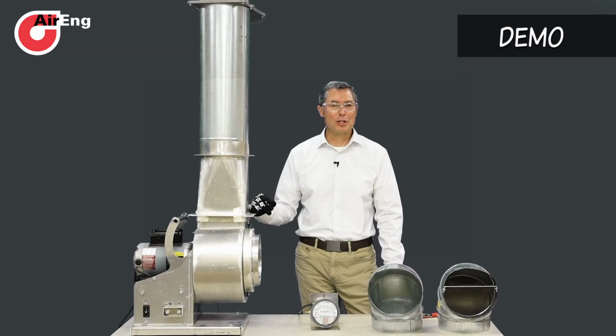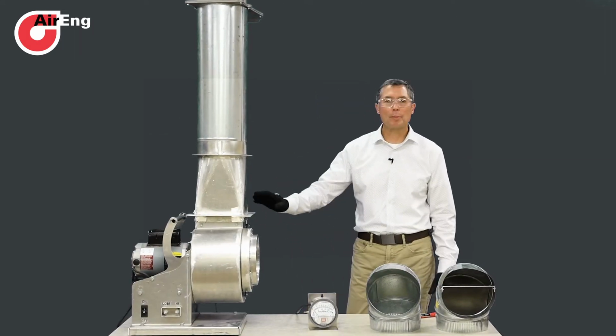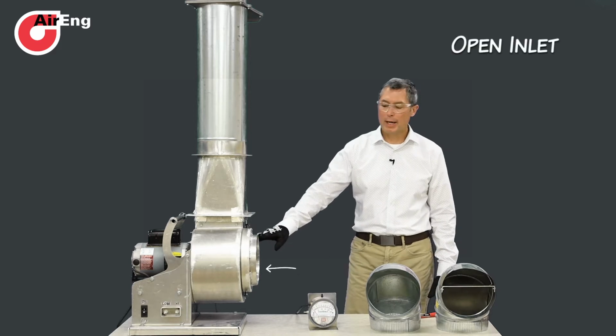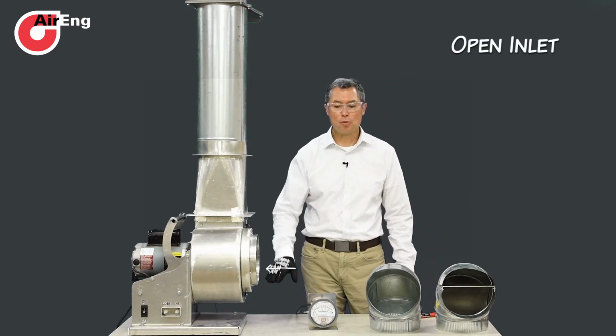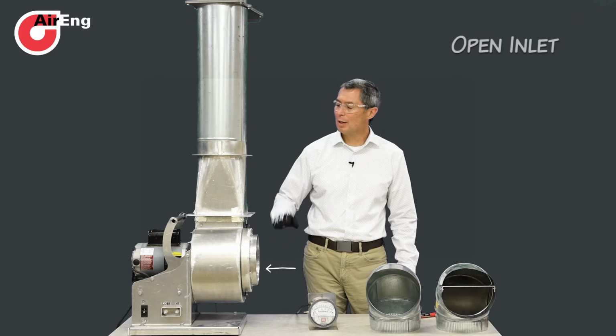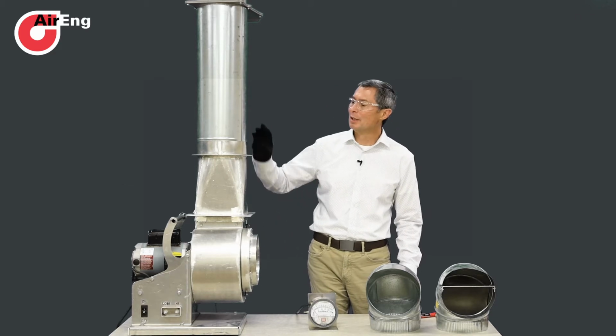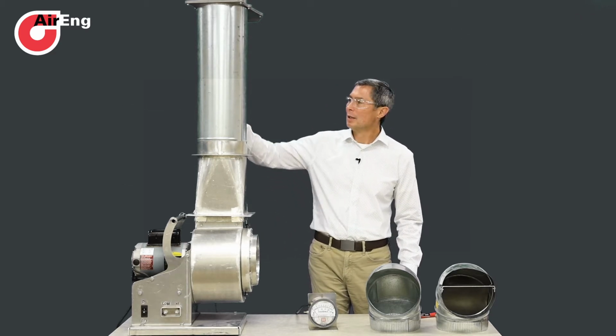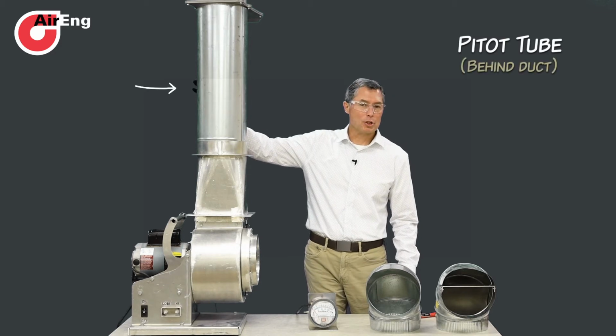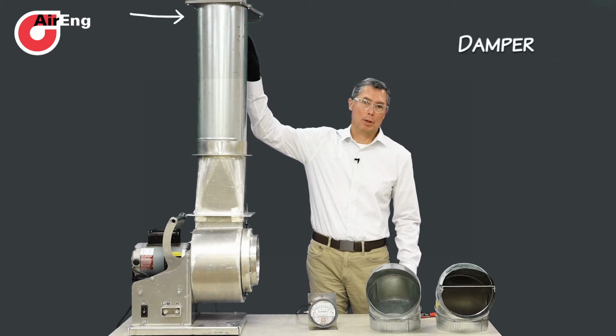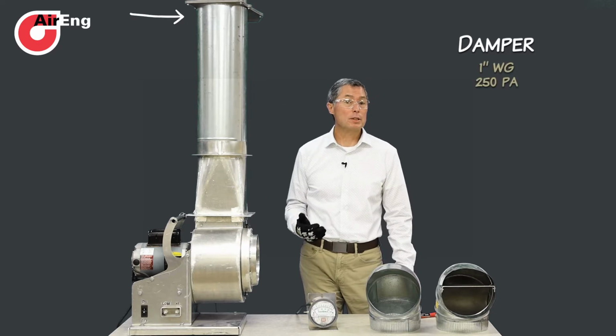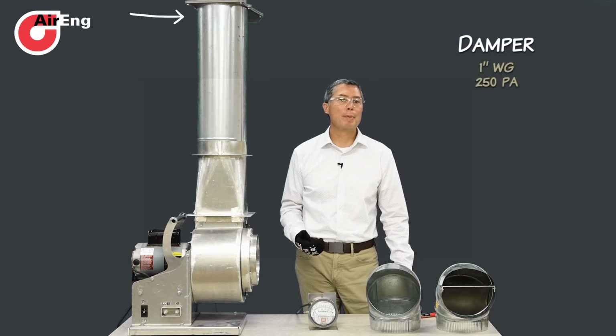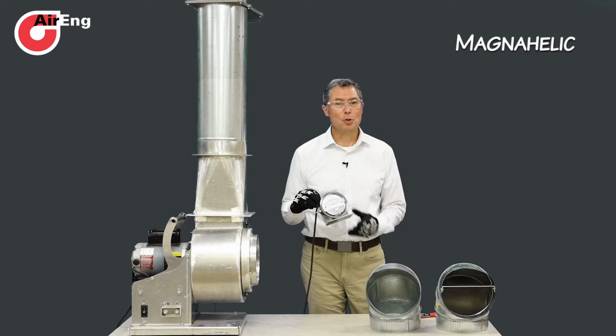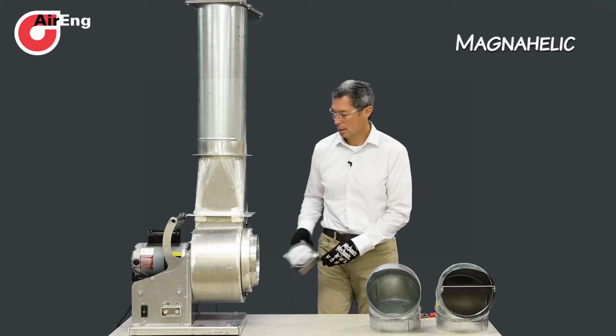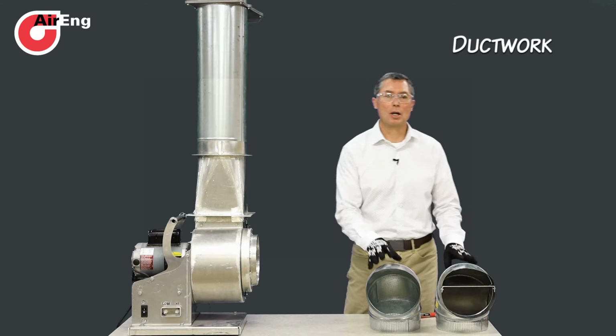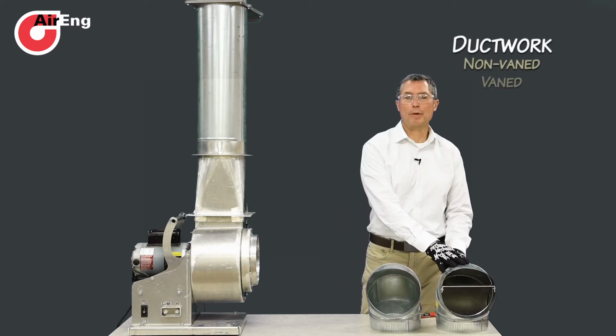Let's move on to the demonstration. But before we do the demo, let's talk about the equipment. We have a centrifugal fan, open inlet, which allows for uniform loading of the wheel with air, a rectangular-to-round transition, a round piece of ductwork, a pitot tube to record the amount of pressure the fan's generating, and a damper to help generate about 1 inch of resistance in inches of water gauge, or about 250 pascals. We also have a little visual meter so you can see what's happening, and two sections of ductwork, one open, one vaned.